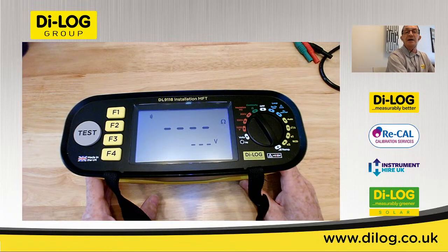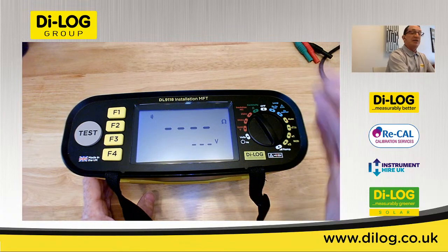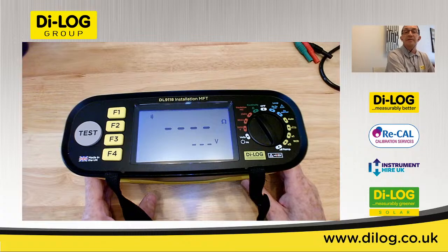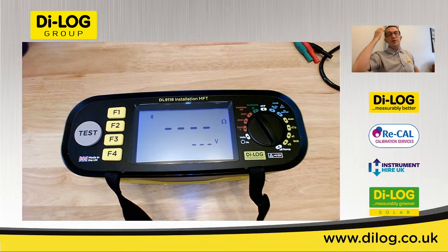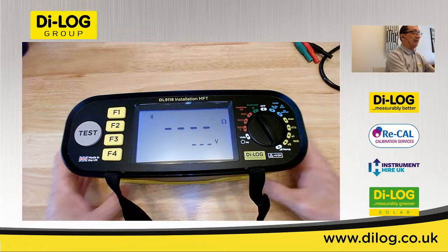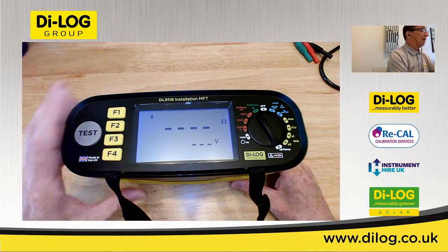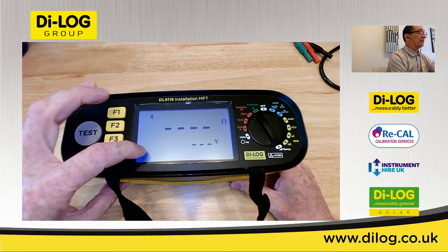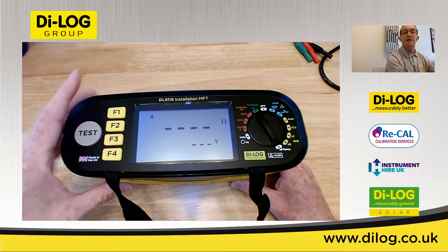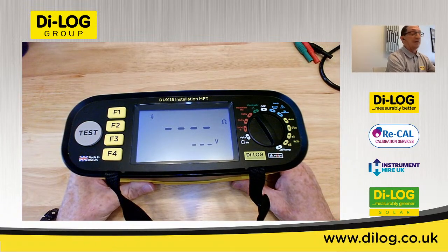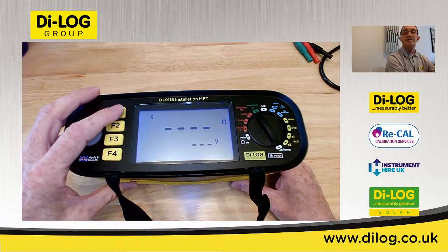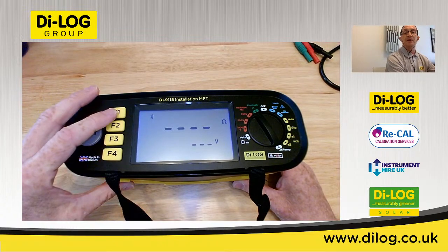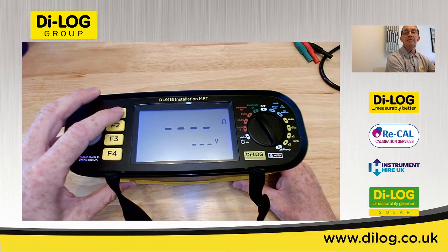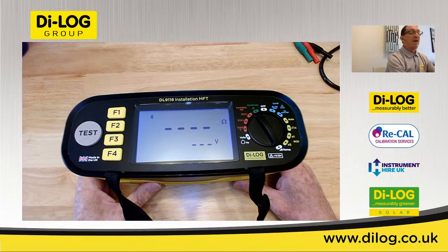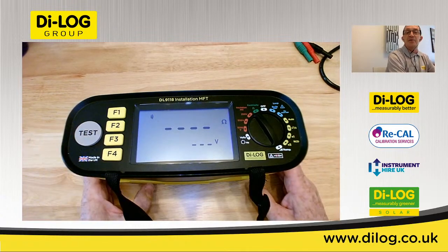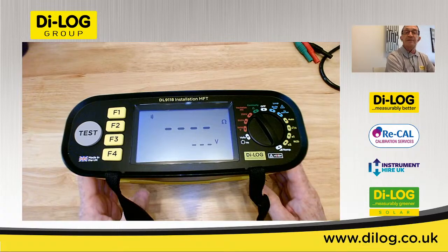Starting on the left hand side with continuity, you can see we've got a very large clear digital display which is also color changing, and I'll come on to that a little bit later too. Anything that appears down the left hand side can be changed using the function keys on the left, as we mentioned. So pressing F1 next to the little continuity buzzer symbol will toggle that on or off. And if you don't want the blue backlight display on all the time, you can also disable that feature too.